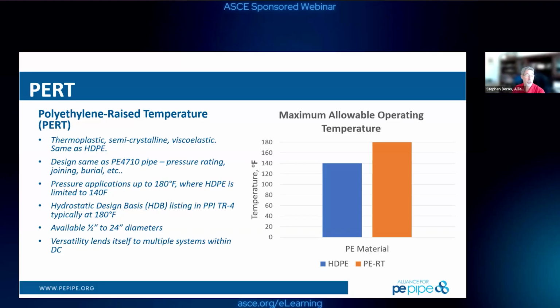On the cold water side, it's the same as regular polyethylene. Regular HDPE that we use every day, PE 4710, can go down to a brittleness temperature of negative 130 degrees Fahrenheit, so you don't have to worry about it on the cold side whatsoever—it still retains ductility. As we get into the other materials, that brittleness really is a key differentiator between HDPE, or polyethylene, and PVC. Is that correct? Oh, absolutely—you would not want to use PVC in these colder temperature environments typically.